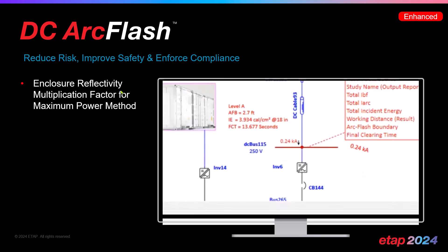Within DC arc flash, we've also added the ability to perform the analysis using constant energy area boundary curves, or as we call them, C area curves. This is a unique capability within ETAP. DC arc flash also includes constant energy area boundary curves in ETAP 2024, or as we call it, C areas. Using the C area methodologies, we can essentially improve the efficiency of the arc flash assessment quite rapidly by automatically updating the minimum and maximum bolted fault currents. And once that is done, you can analyze numerous arc flash input data variations without the need for creating any additional scenarios. And by creating various combinations of the input data variations and using maximum and minimum short circuit currents, you can get a boundary point, a curve, or an area of energy that gives you an indication of the possibilities of the fluctuation of the arc energy under various conditions.